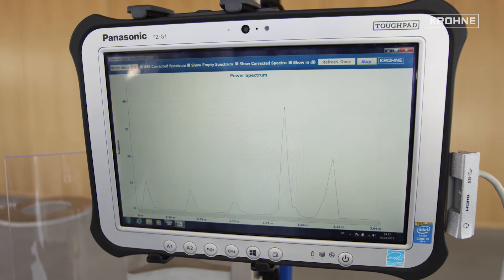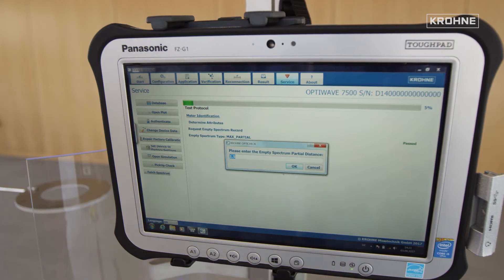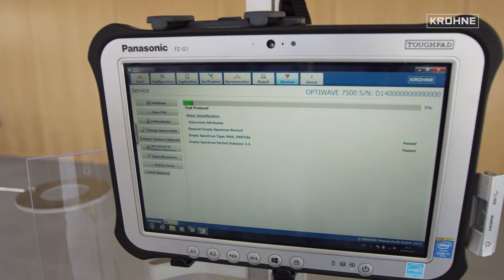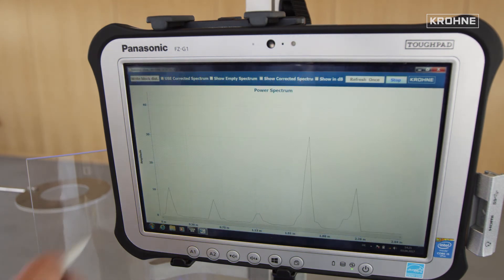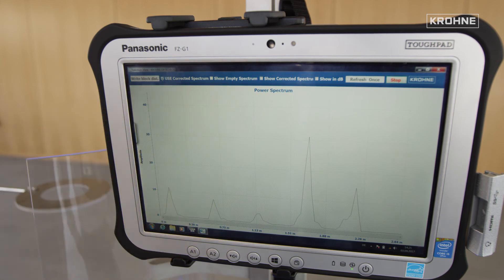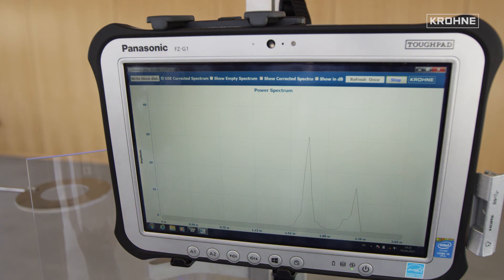If such a disturbance is caused, for example, by installations in tanks, there are two possibilities for optimization. Firstly, the disturbance can be hidden by recording an empty spectrum. For this purpose, the received radar signal of the empty tank is recorded and stored into the memory of the radar device, and then subtracted from each subsequent measurement.